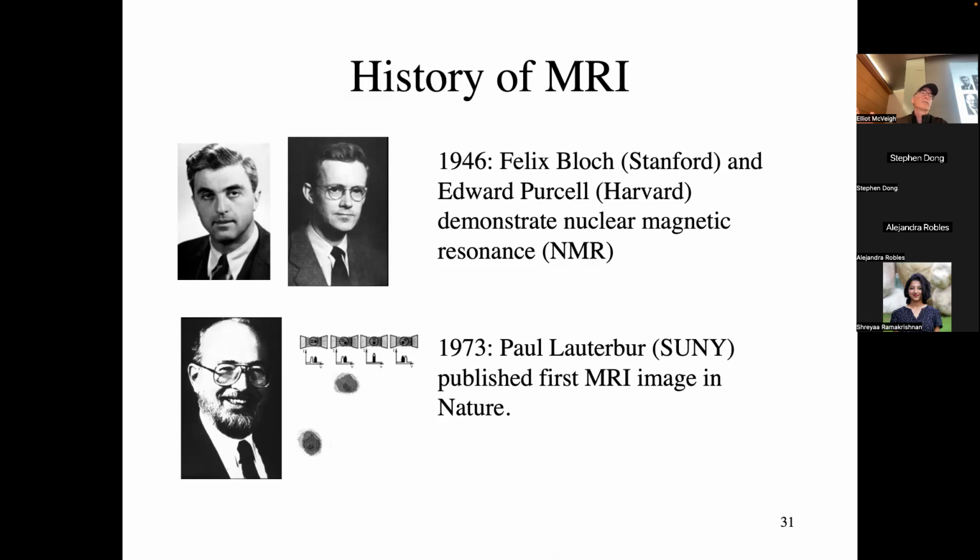And in an NMR spectrometer, usually what you do is you have some chemical composition, and it will give off different frequencies for different hydrogen and carbon and stuff in different parts of the molecule. In order to do that well, you need to have the system at exactly the same field strength everywhere for your sample.